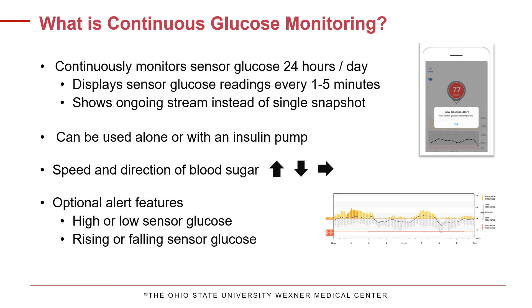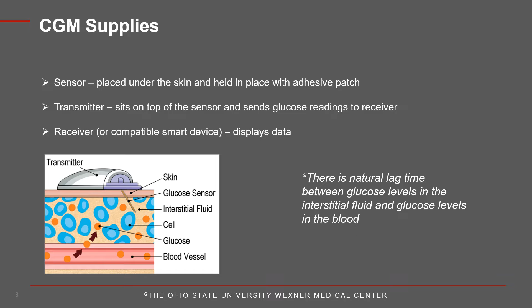There are 3 main parts to the CGM system. The sensor is the piece that is placed directly under the skin and held in place by an adhesive patch. The transmitter wirelessly sends the glucose reading to the receiver. Lastly, the receiver, which may also be your smartphone if you have compatibility with the app, will display your sensor glucose data. The sensor is measuring the interstitial glucose level, which is the glucose that is found in the fluid between the cells. Due to this, the sensor data can be approximately 5 to 10 minutes behind the actual blood glucose level.